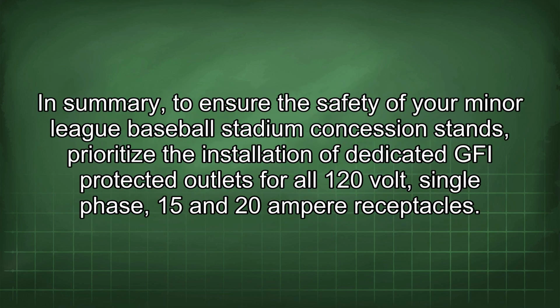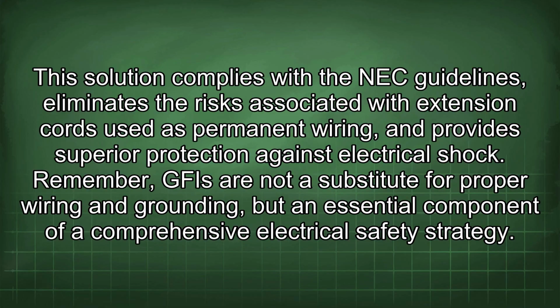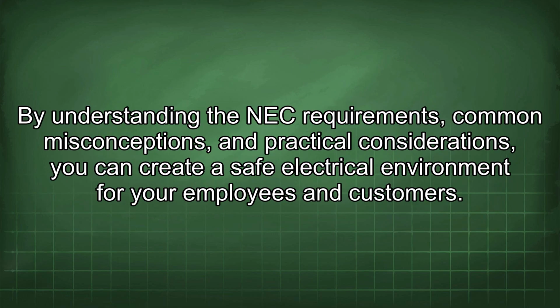In summary, to ensure the safety of your minor league baseball stadium concession stands, prioritize the installation of dedicated GFI protected outlets for all 120-volt single-phase 15 and 20 ampere receptacles. This solution complies with the NEC guidelines, eliminates the risks associated with extension cords used as permanent wiring, and provides superior protection against electrical shock. Remember, GFI are not a substitute for proper wiring and grounding, but an essential component of a comprehensive electrical safety strategy. By understanding the NEC requirements, common misconceptions, and practical considerations, you can create a safe electrical environment for your employees and customers.